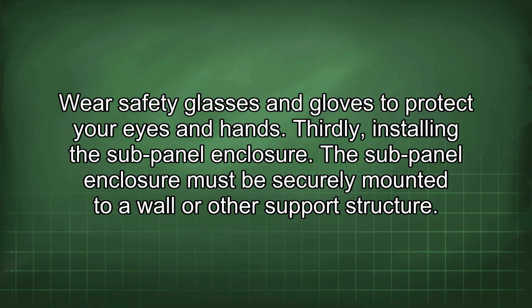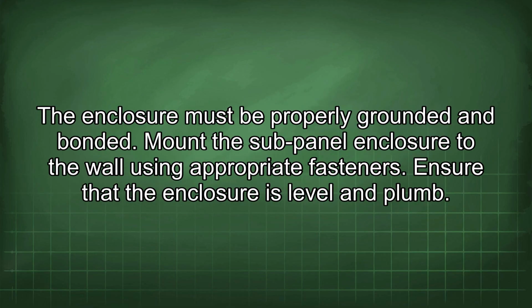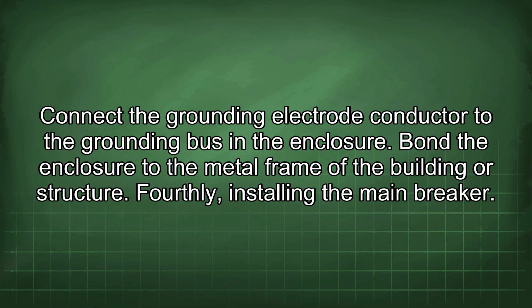Thirdly, installing the sub-panel enclosure. The sub-panel enclosure must be securely mounted to a wall or other support structure. The enclosure must be properly grounded and bonded. Mount the sub-panel enclosure to the wall using appropriate fasteners. Ensure that the enclosure is level and plumb. Connect the grounding electrode conductor to the grounding bus in the enclosure. Bond the enclosure to the metal frame of the building or structure.